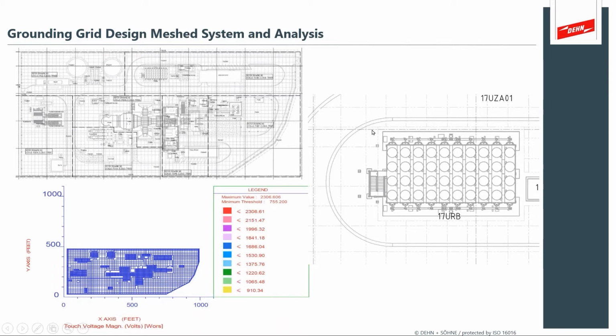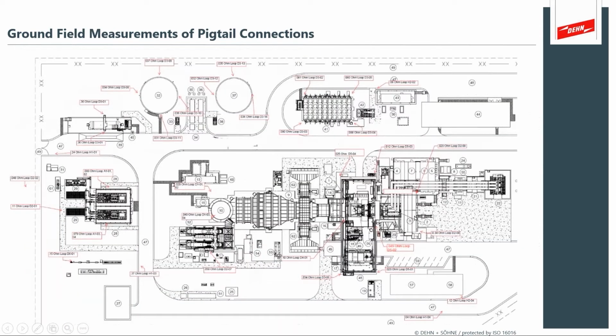And then we have a little bit of a zoomed in illustration where you can see the large mesh that's across this plant, and then what looked like ring grid, like that type B earthing ring around each of these structures. And so this is part of your entire lightning protection system. So we talked about the air terminals, we talked about the down conductor systems, and of course you have to have that all connected to the earthing grid. This is what we see as a final result on that type of typical plant.